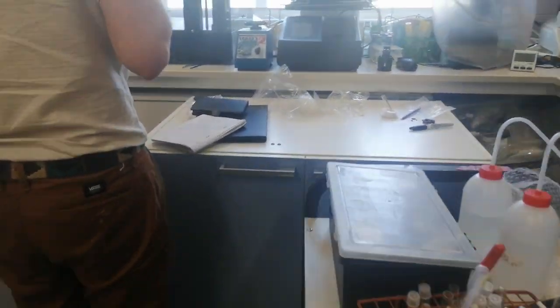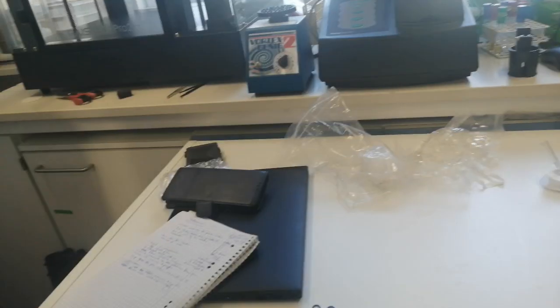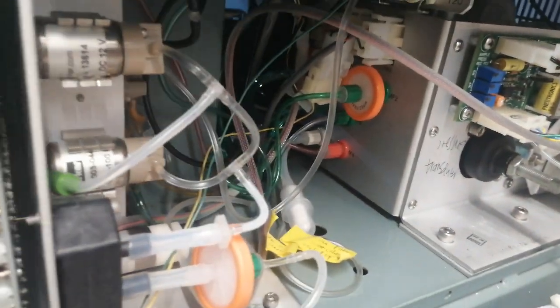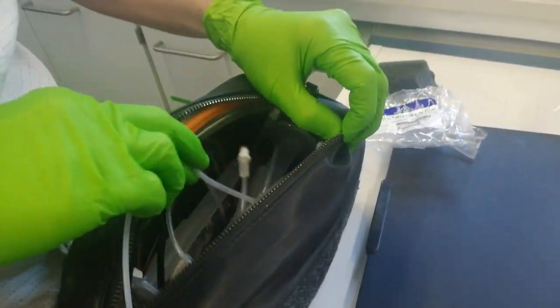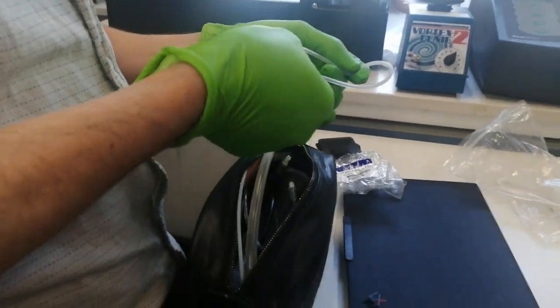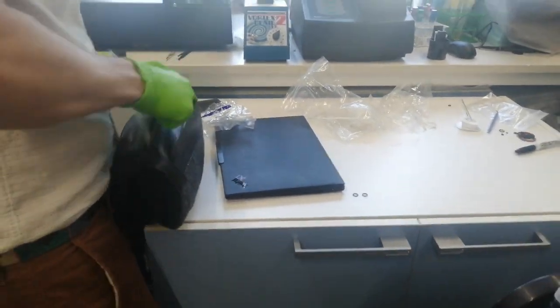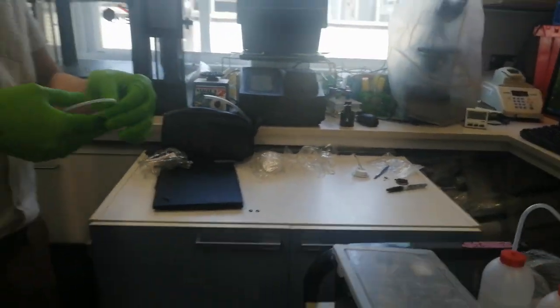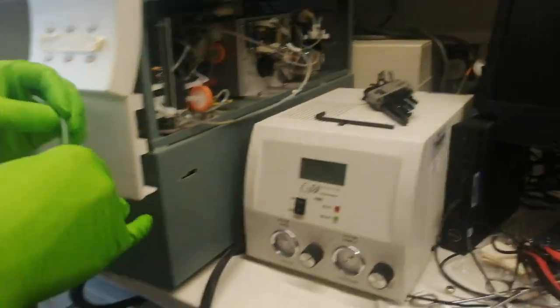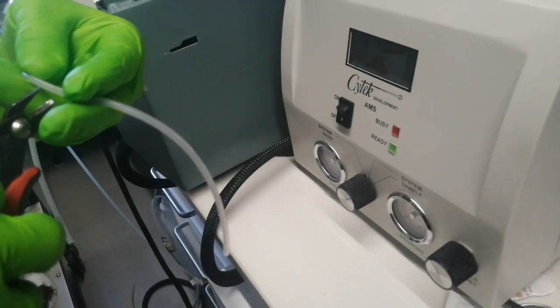So yeah, there's the pinch valve tubing, which wasn't in the kit, and that is one of the last parts. The other part I already changed was the other piece of tubing, the peristaltic pump tubing. Sorry. Oh yeah, of course. So I should have some here. There it is. That will do. Yes, that was the one. So this is soft silicone tubing, and this is too long really, so I'll just cut that in half, and you can keep the other bit.